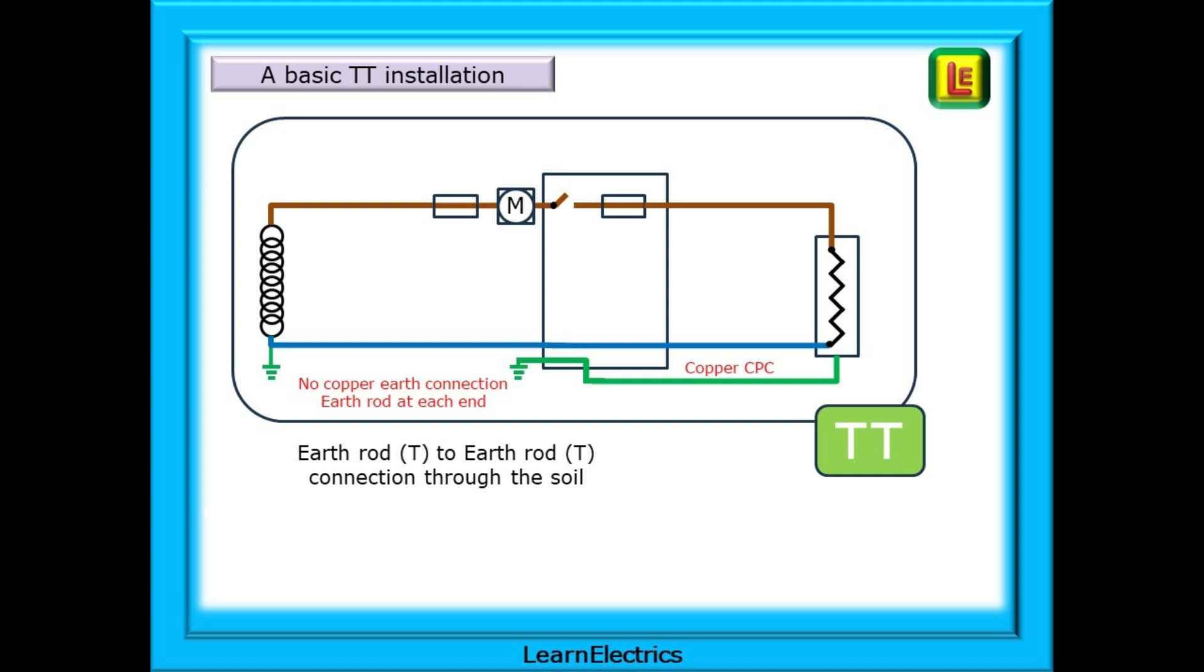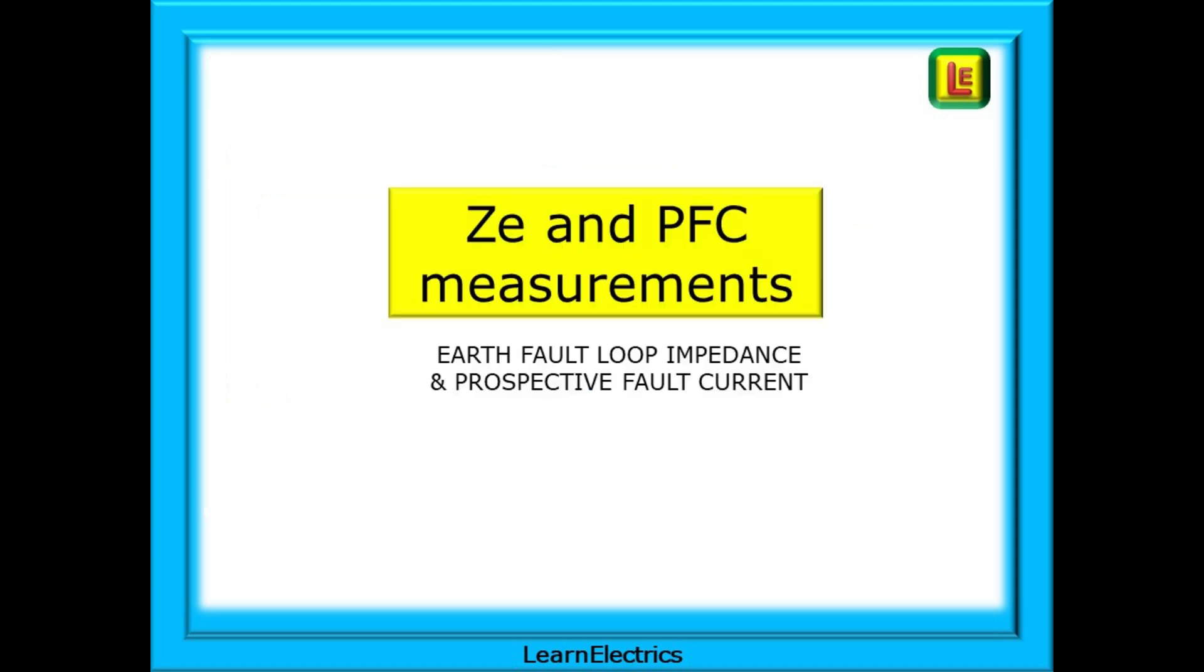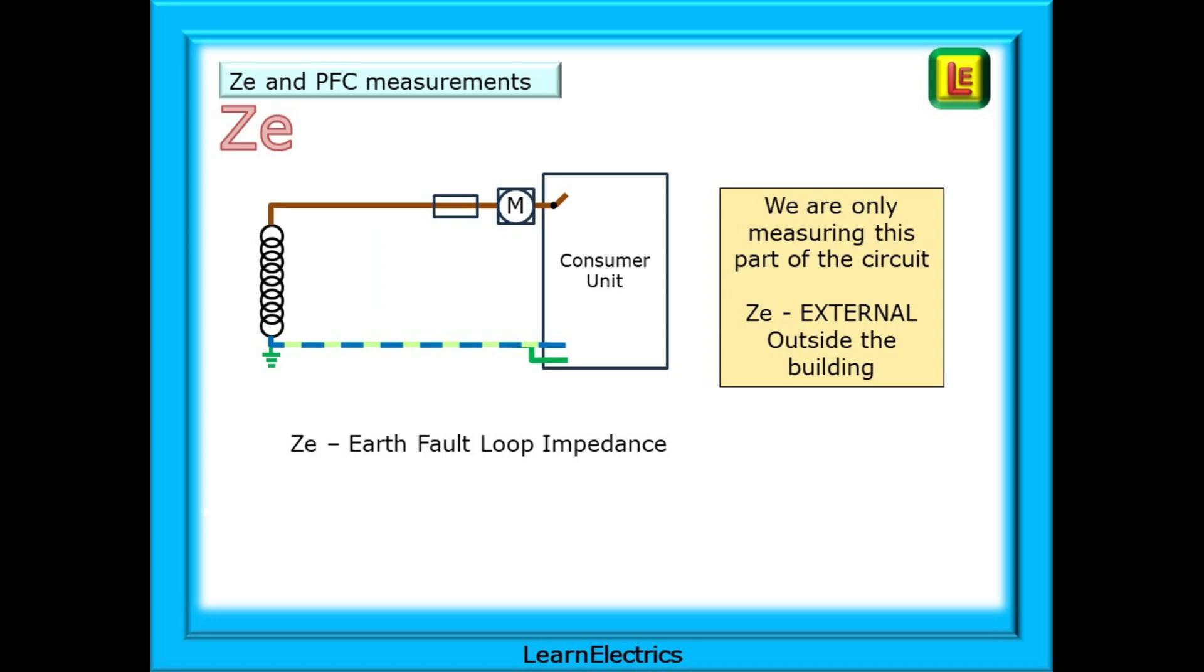If we look now at ZE and PFC measurements we will see that ZE or earth fault loop impedance to give it its full name and prospective fault current are two corners of the same ohms law triangle. We call it impedance and not resistance because ZE is measured on a live AC system. Taking ZE first, if we think of the installation drawings from the first few slides, this drawing shows just the part that is tested for ZE to make it easier to understand.